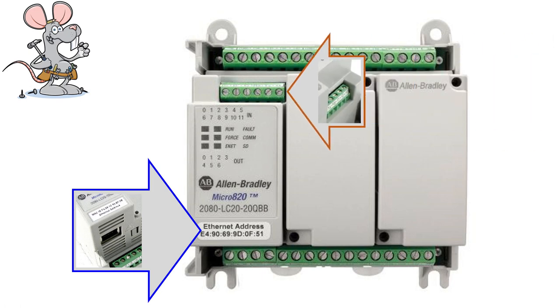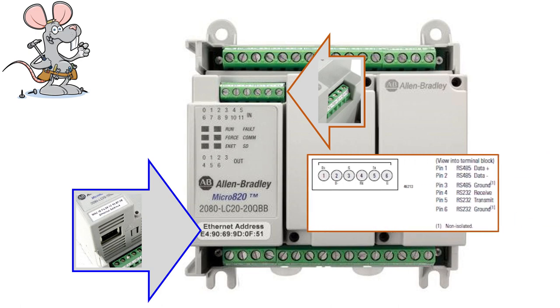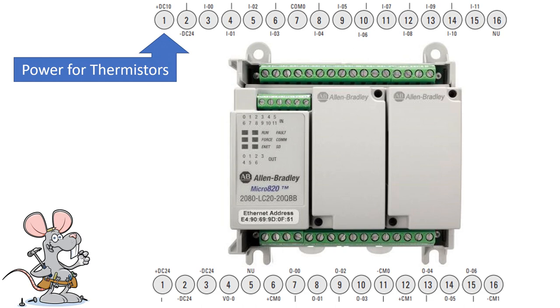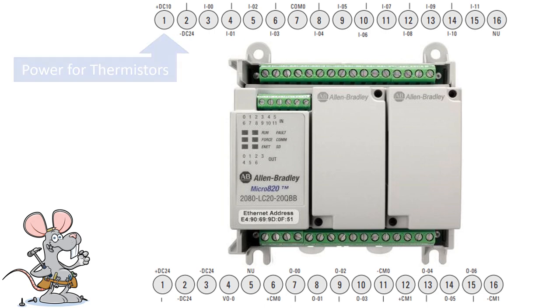It has an RS-232/485 port with six terminals — three terminals for RS-232 (pins 4, 5, and 6) and three for RS-485 (pins 1, 2, and 3). These are the screw terminals starting at the top. The input terminal strip is at the top: terminal 1 is plus DC 10 volts, which is an output power supply for thermistors. You have 12 inputs, and inputs 0, 1, 2, and 3 are shared between digital and analog.